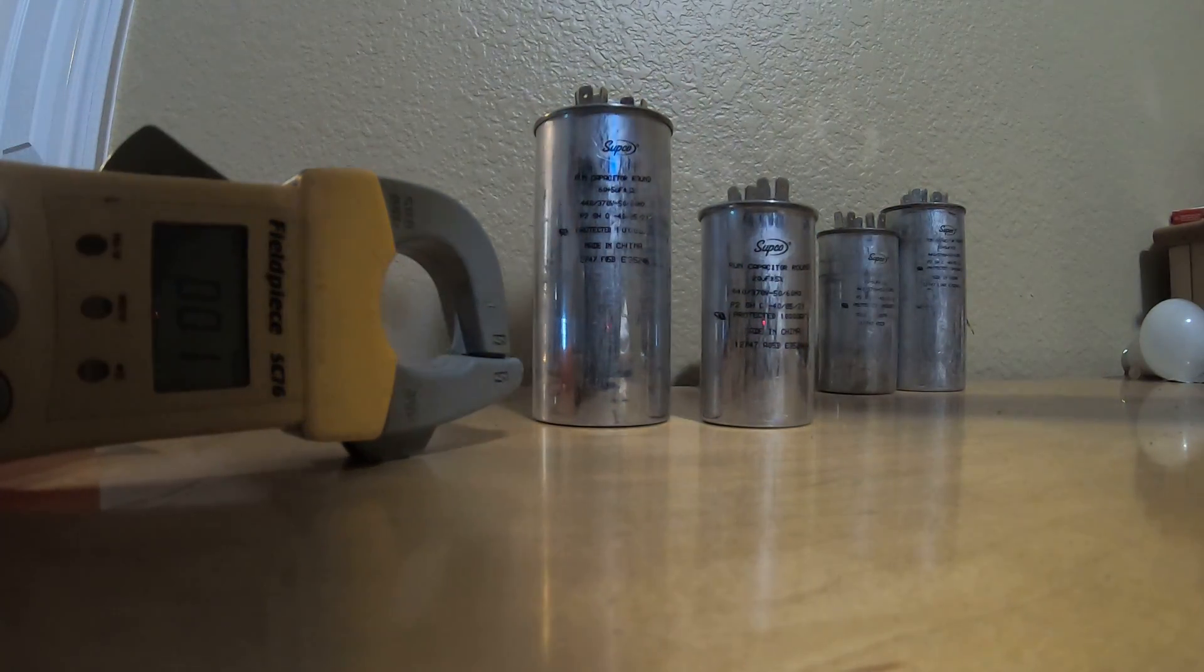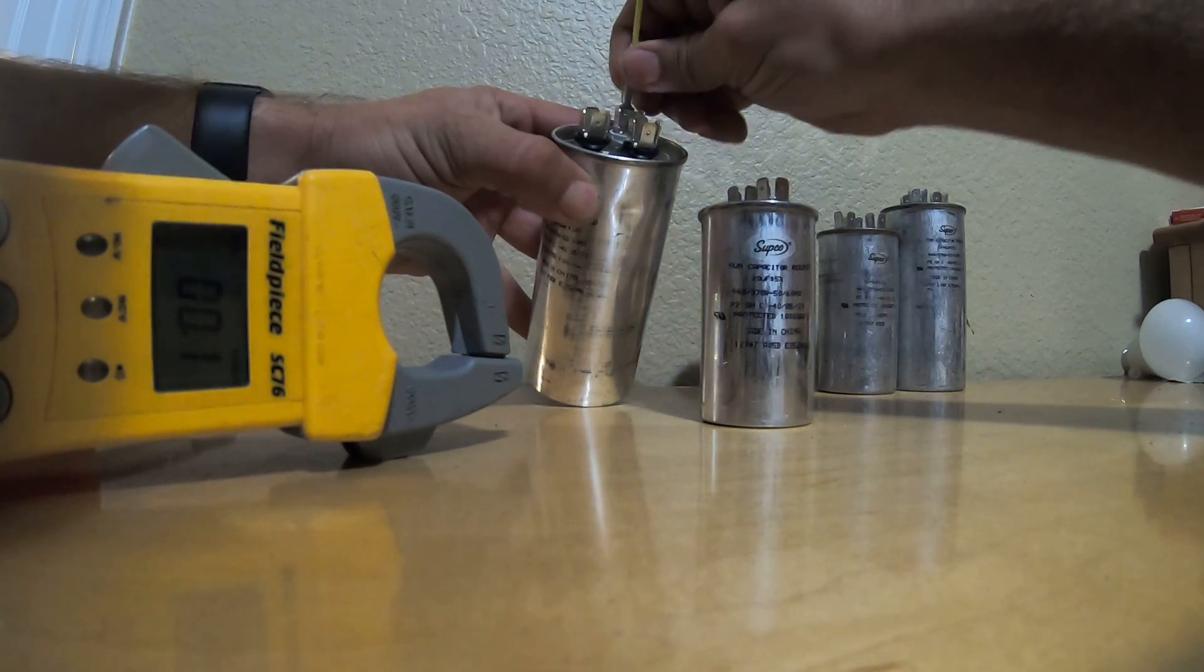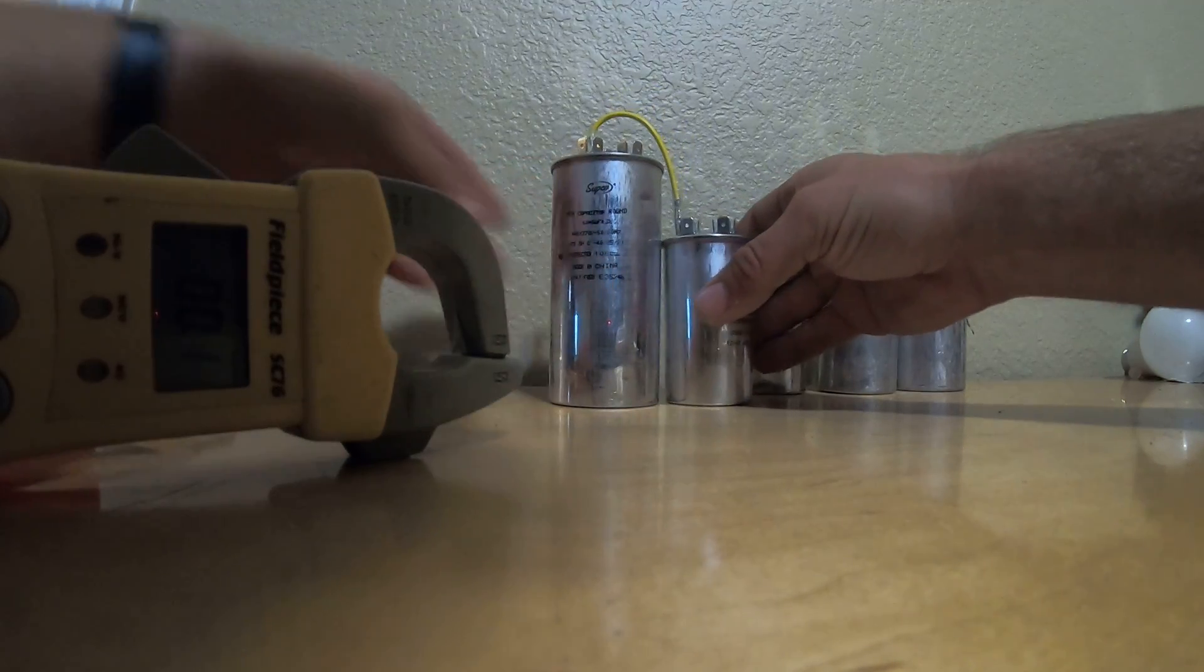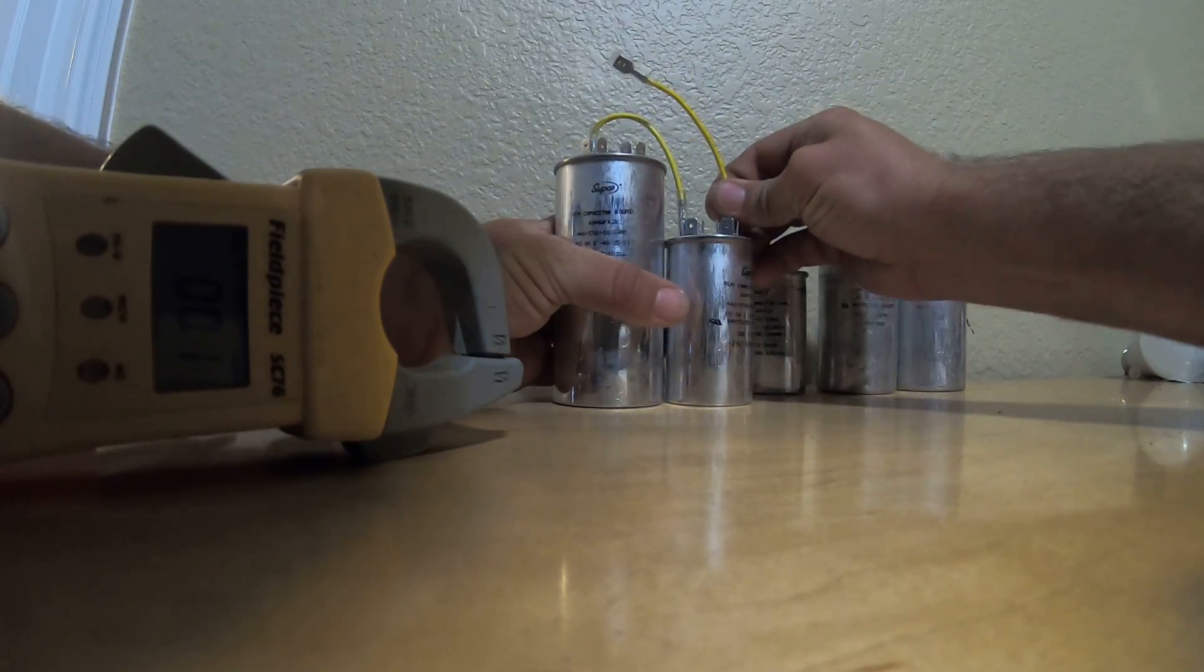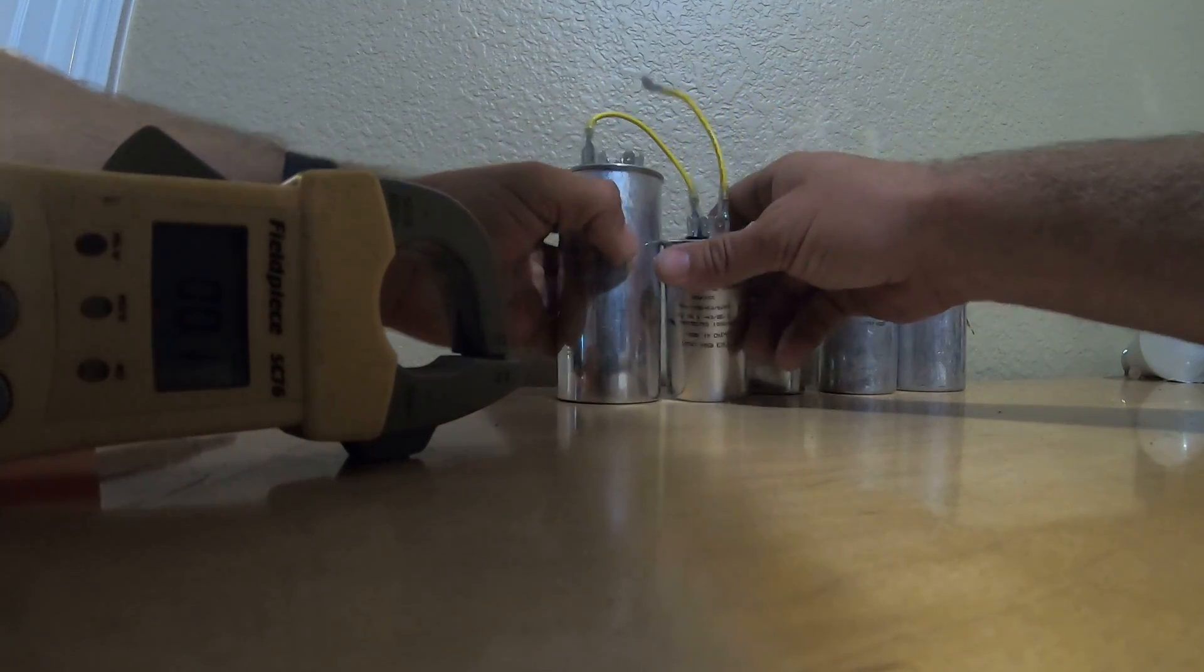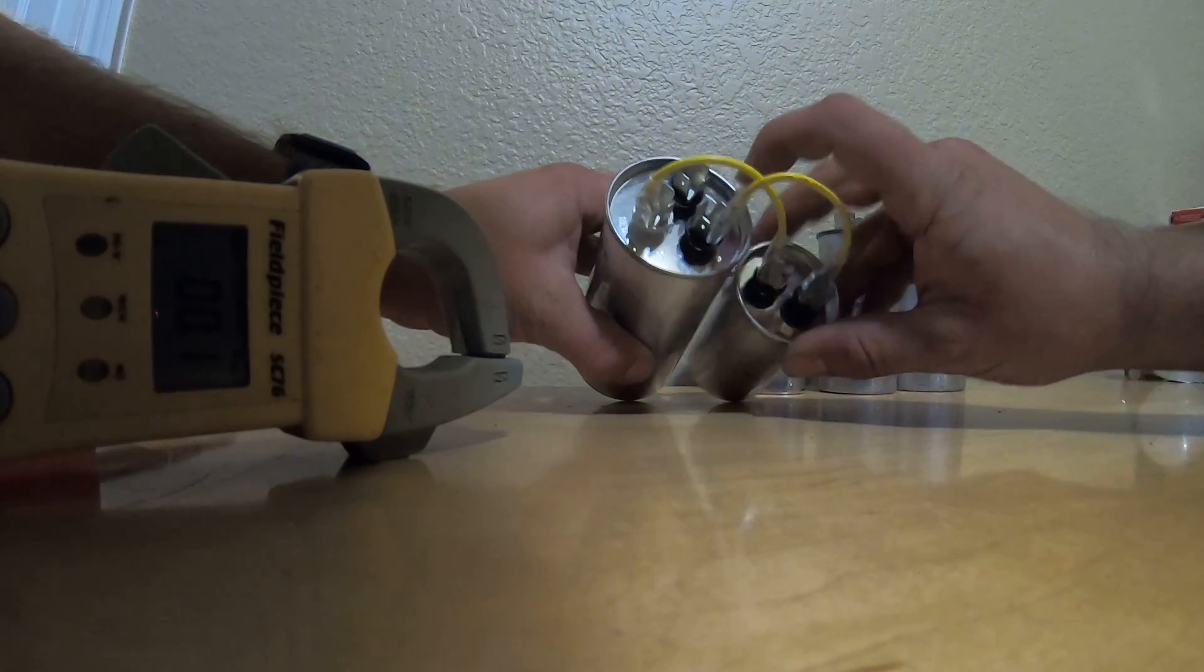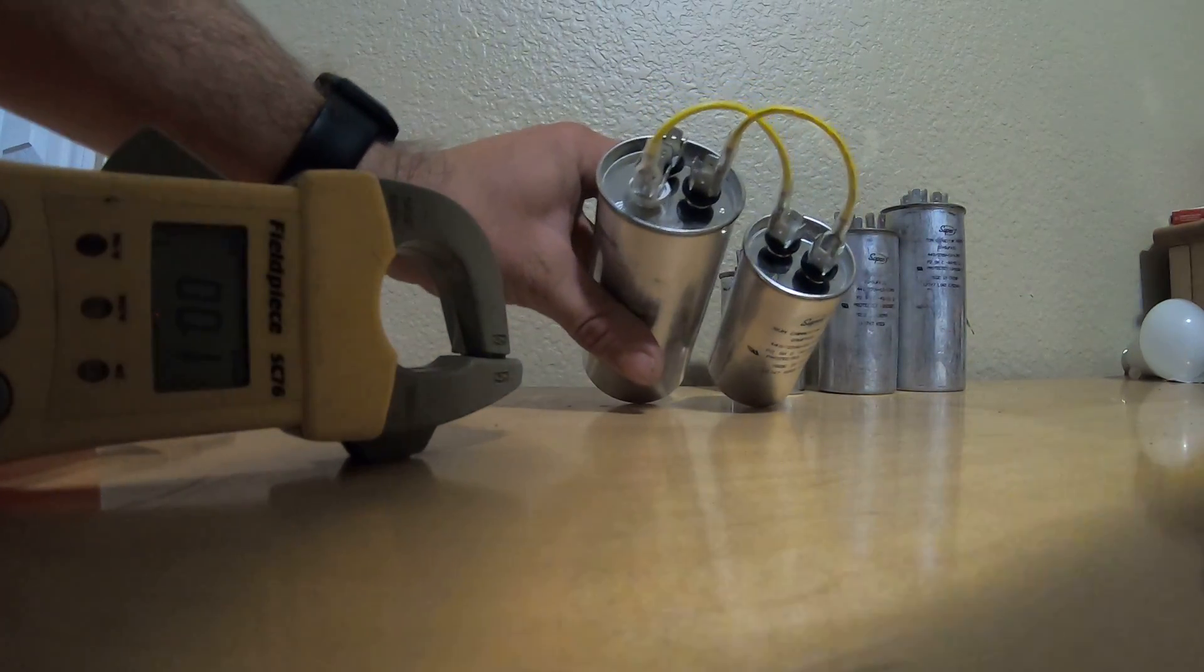So I have a 60 and I also have a 20 microfarad. If I needed an 80 for some reason and this is all I had, what I would do is I would take this and jump it from the Herm side right here over to one side of the 20 microfarad capacitor, like that. Then you take the other side of the split capacitor and you take it to the common terminal. Move it over here a little closer.